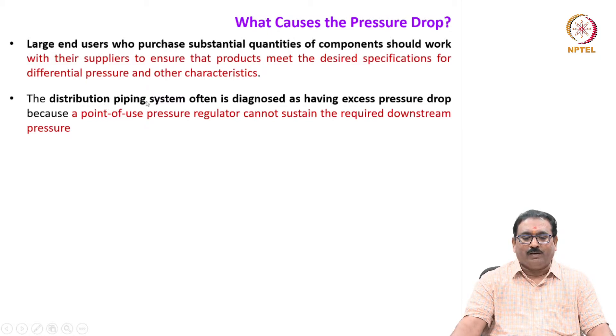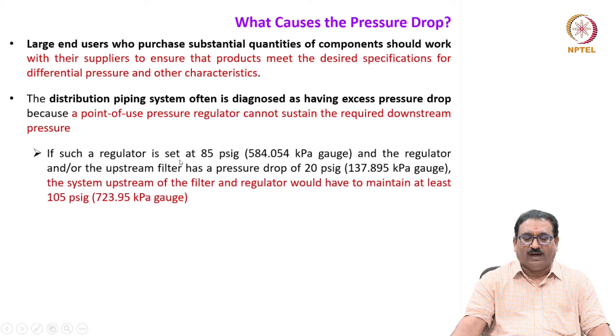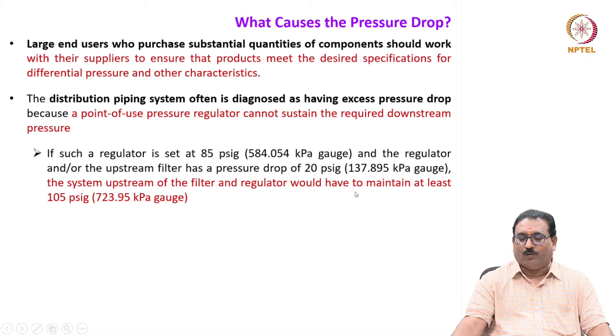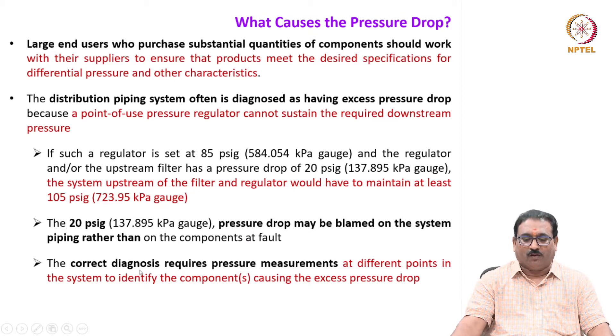The distribution piping system is often diagnosed as having excessive pressure drop because a point-of-use pressure regulator cannot sustain the required downstream pressure. If such a regulator is set at 85 PSIG and the regulator or the upstream filter has a pressure drop of 20 PSIG, the system upstream of the filter and regulator would have to maintain at least 105 PSIG. The 20 PSIG pressure drop may be blamed on the system piping rather than on the components at fault. Correct diagnosis requires pressure measurement at different points in the system to identify the component causing the excessive pressure drop.